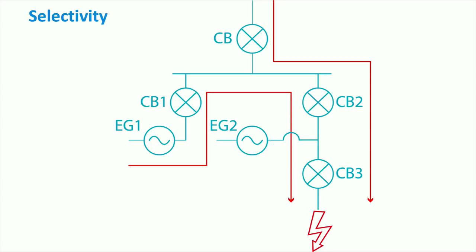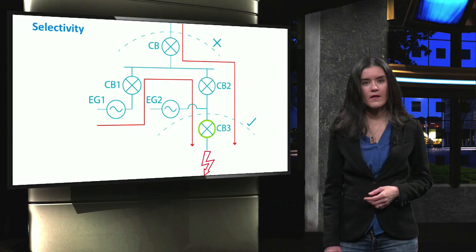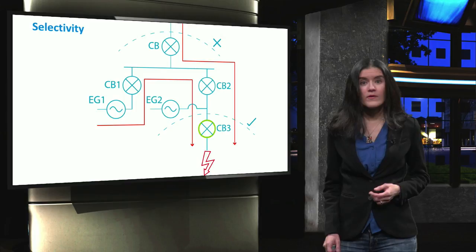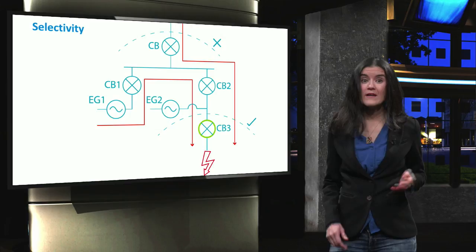If this happens, then the selectivity criterion is met, because only a minimal section of the power system is affected by the fault. However, if circuit breaker 3 is not properly operated, then circuit breaker 2 shall be disconnected. When the disconnection of circuit breaker 2 takes place, also generator number 2 is disconnected.